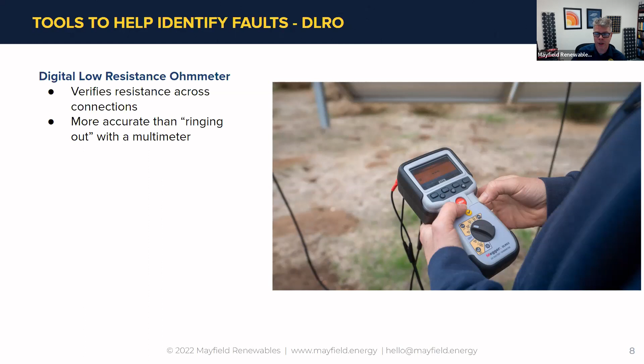I think one of the biggest hurdles with connectors is the energized aspect. If you're checking connection to connection in an array or string that has voltage present, most tools don't have the ability to measure on a live circuit, and that's one of the biggest hurdles to overcome. Also, checking a few connections on a residential application is much different than checking thousands upon thousands at utility scale, so it becomes a matter of speed. It's an efficiency and safety thing, but crews are also trying to move fast throughout the array, so doing it quickly is an important part.